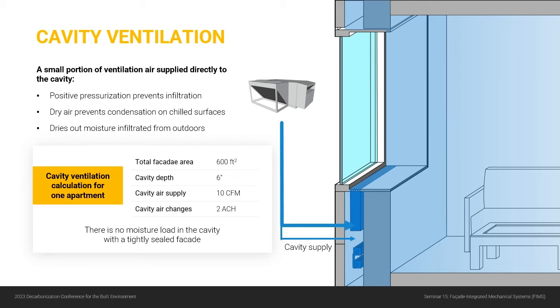And then the other thing it does is, the facade should be watertight, but if water does get in there, maybe if you have some kind of extreme rainfall event or something, however water gets in there, you can dry it out relatively quickly because we're constantly supplying this dry air into the cavity. And so that cavity is a relatively small volume. So for a 2-bedroom apartment, with the amount of cavity volume you have, all you would need to do is supply 10 CFM into that cavity to get 2 air changes per hour. So you can get very effective drying and pressurization.